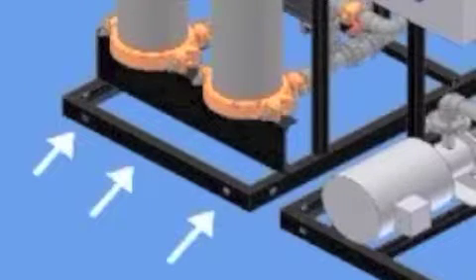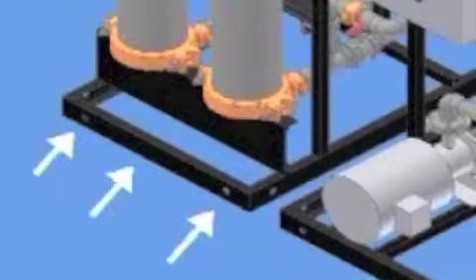Use a concrete drill bit to drill a 7-centimeter or 3-inch deep hole at each of the corners of each skid. If the floor is steel, create a weld bead every 2 feet or so or as required once all the shims are in place. Also, weld the shims so they cannot be removed.